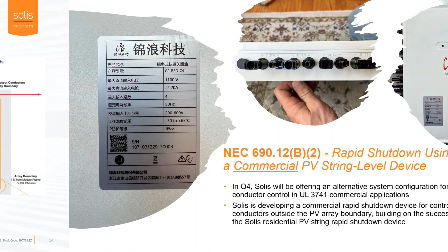Now, as I said, the typical solution for this kind of thing is to put the actual inverter right up there within the array field. And you can then use, let's say, a NEMA 4X AC switch right on the side of the inverter to essentially disconnect the PV system conductors outside the array boundary, which in this case would be the inverter conductors outside. So now by shutting down the inverter, you have set the PV array into open circuit, and you have shut down the conductors leaving the PV array and going down to the point of connection. And so typically this is done with the inverter right there within the array boundary, mounting the whole inverter right up there next to the PV modules.